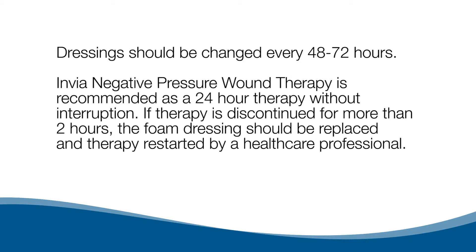Invia negative pressure wound therapy is recommended as a 24-hour therapy without interruption. If therapy is discontinued for more than two hours, the foam dressing should be replaced and therapy restarted by a healthcare professional.